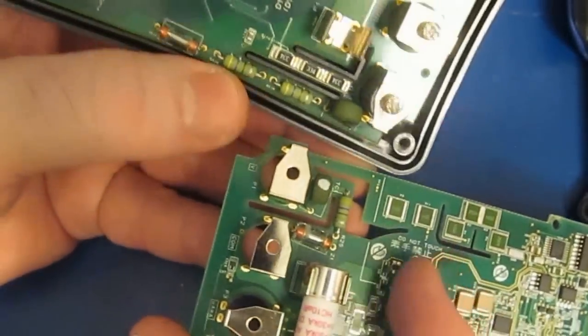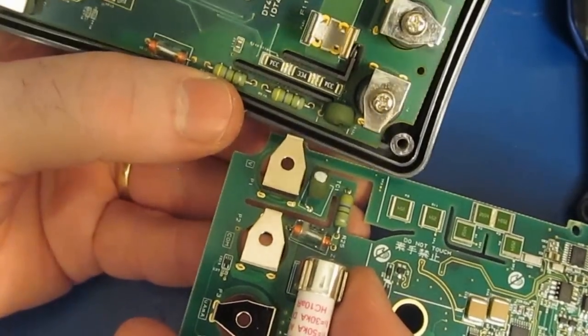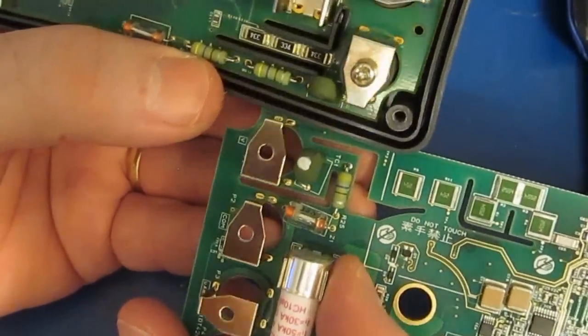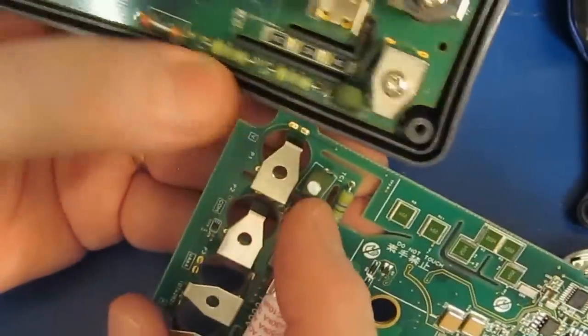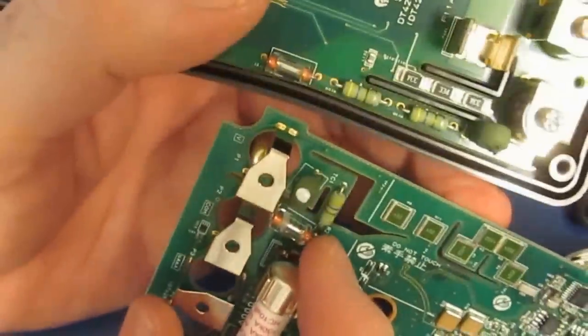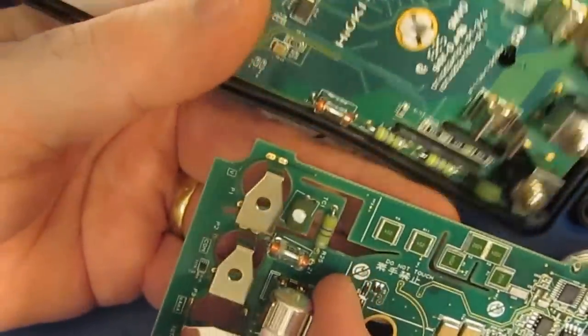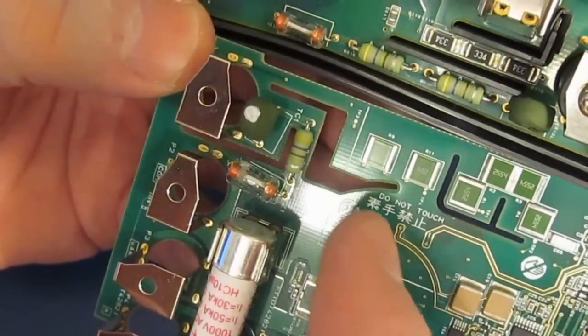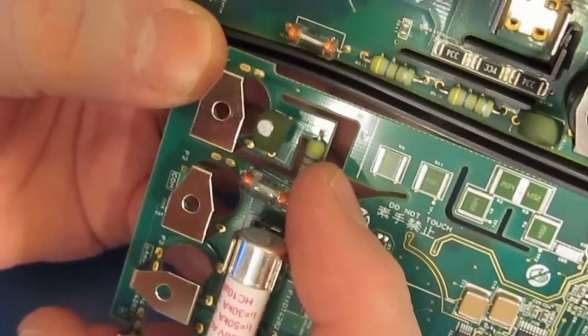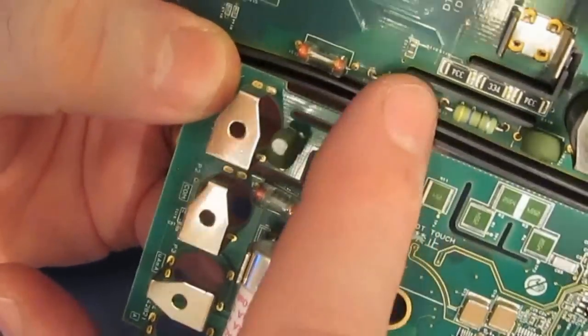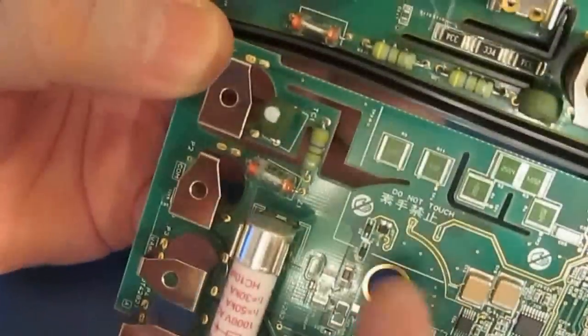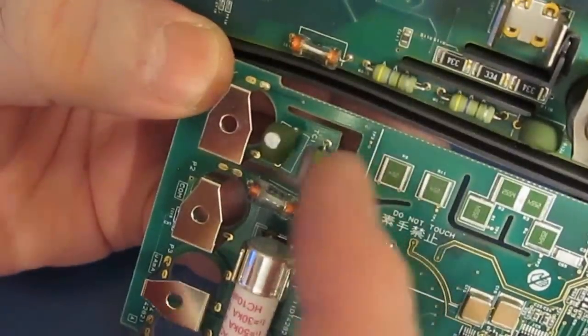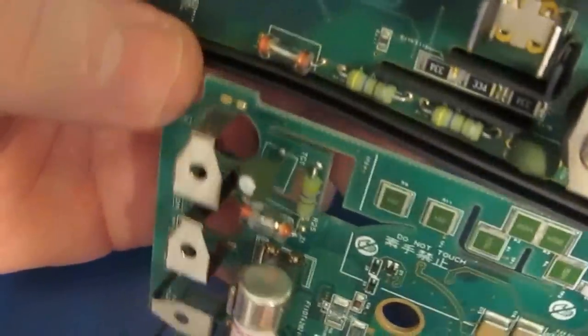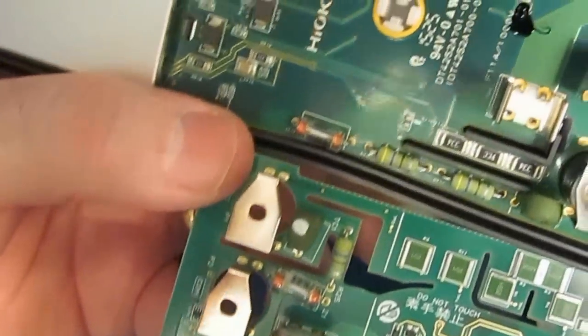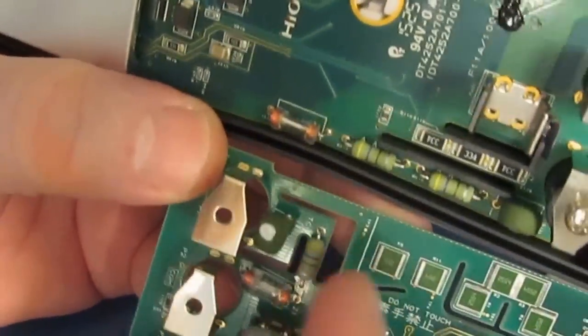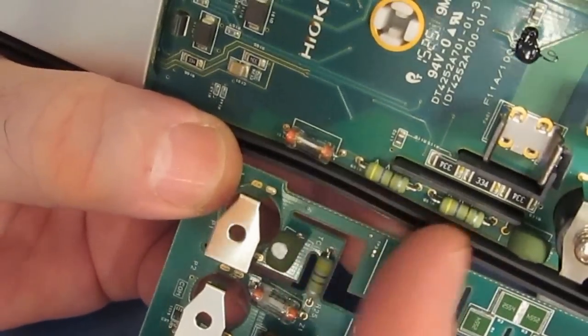Here are the two PTCs. You'll notice the package size is basically the same, and it looks like they use the same gas discharge tube. But notice the surge rated resistor: here we have a single part, and here we have two in series. I don't know what possessed them to remove the one part. They must have felt they could get away with it, but the breakdown voltage is going to be cut in half here.